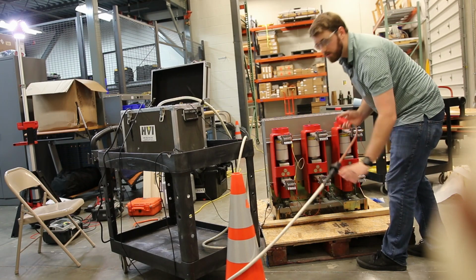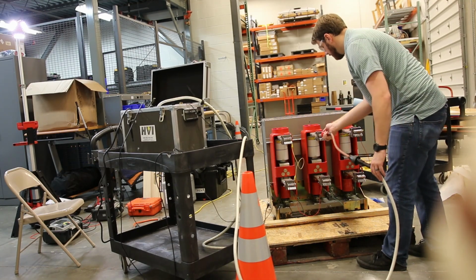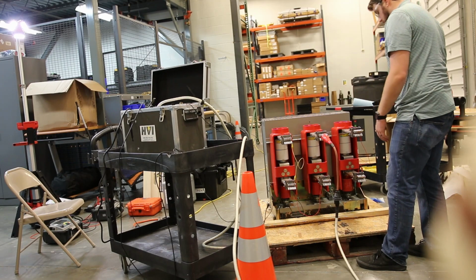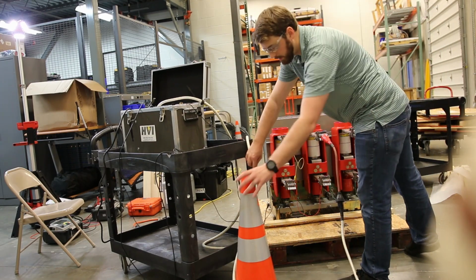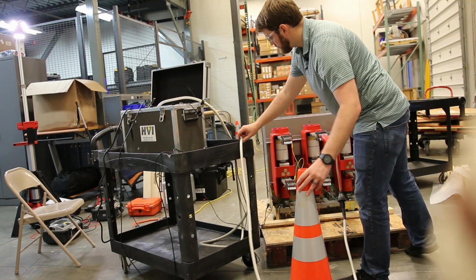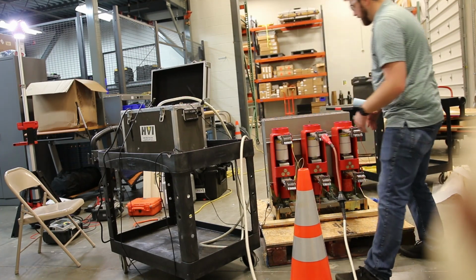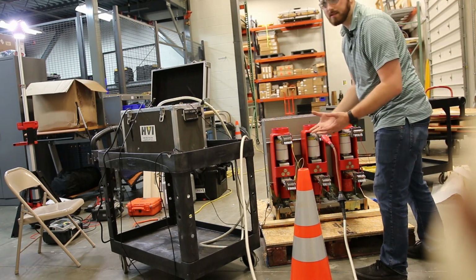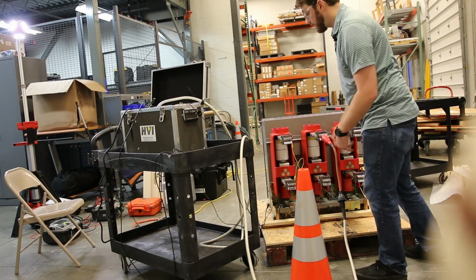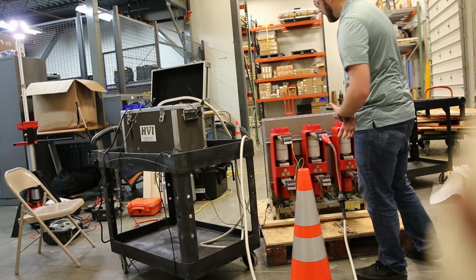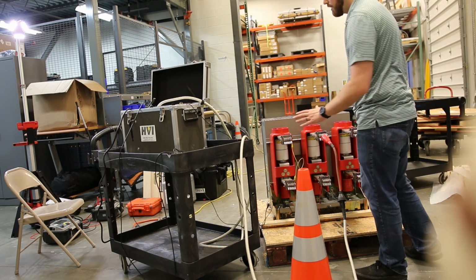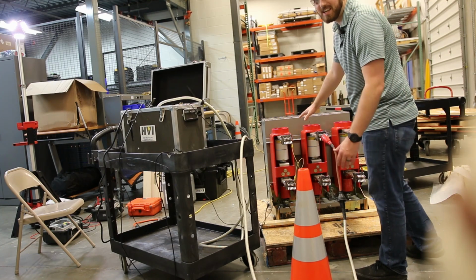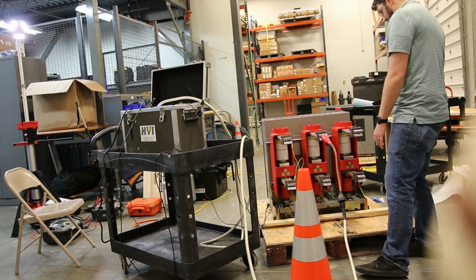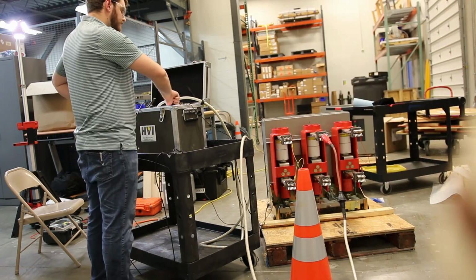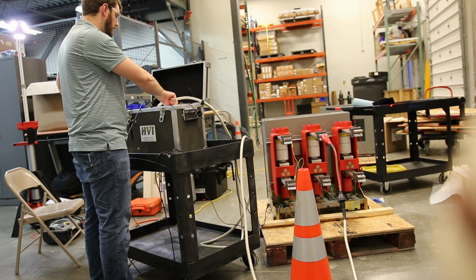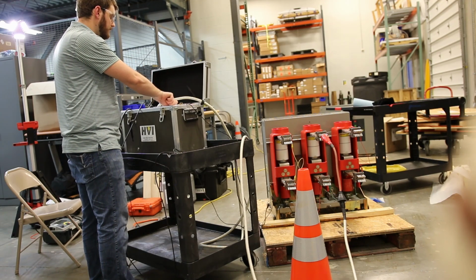On something bigger, or something that had a lot of capacitance, like an overhead bus duct or a large transformer or cables, whenever you're doing an energized test, you're applying a lot of voltage to something, and there's a chance that what you're testing is holding a charge, so you always want to ground it out. This is pretty small, it's on a pallet, it's sort of isolated. I'm not super worried about it, but don't go touching it while the test set's on, because it'll light you up and it hurts. We're going to ramp the voltage up until we get to about 14 kV.